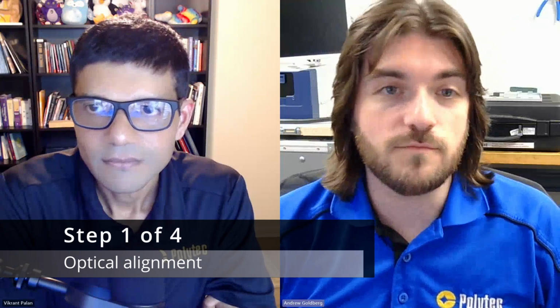Yeah, sure. It's very similar to what we do on the single point systems. We'll usually start with an optical alignment and optics and laser health check, make sure nothing's broken. The laser has good output through the system, depending on which version it is, be it the HeNe or the IR systems. They have different requirements. We make sure that everything matches our requirements in the specs.